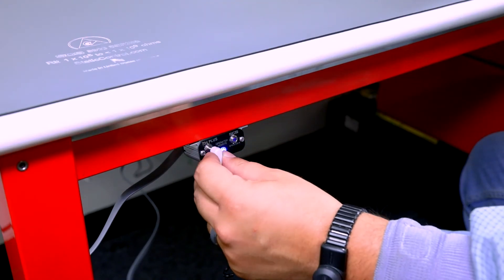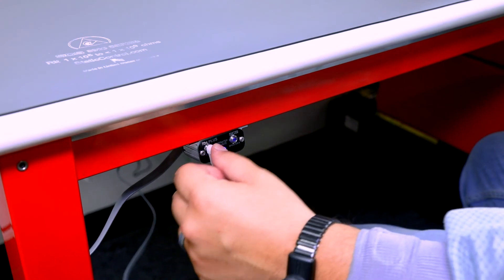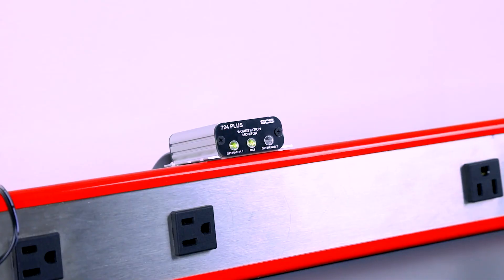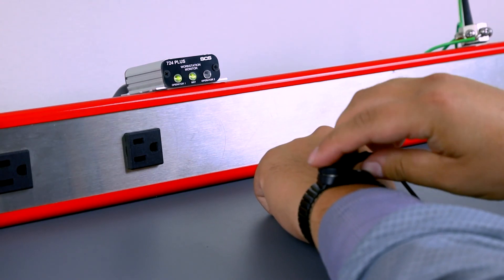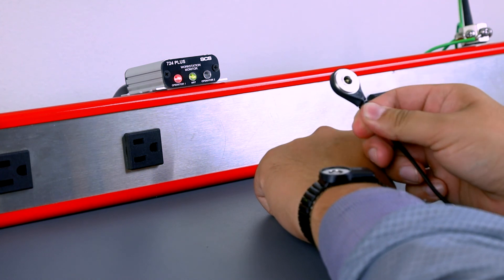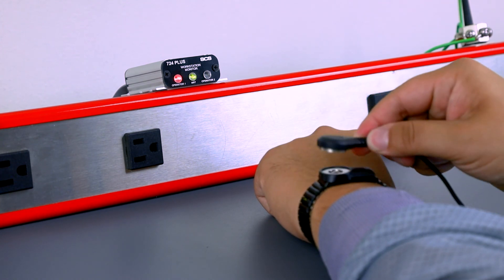The 724 Plus Monitor is now fully installed and ready to monitor an operator. Install a dual wire wrist strap snugly to the wrist. Connect the cord to the wrist strap and plug the wrist strap cord into the operator jack on remote. The operator is now grounded and being monitored by the 724 Plus Monitor.